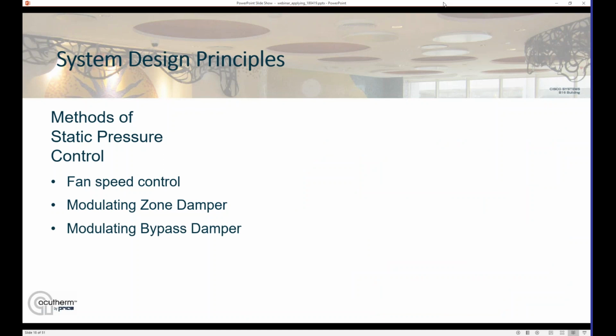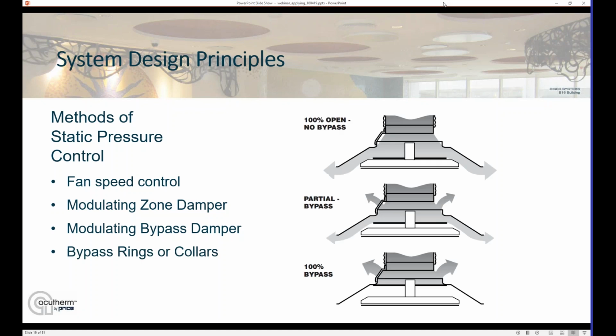This can also be done with a bypass instead of a modulating zone damper. If you do have a constant volume system, then you have to use a bypass, because you've got to keep the air going somewhere. So instead of that modulating damper being in line with the zone of diffusers, it's run between the supply and the return ducts, and now as the diffusers start to close toward minimum, that bypass would open up and keep the air flowing back around.